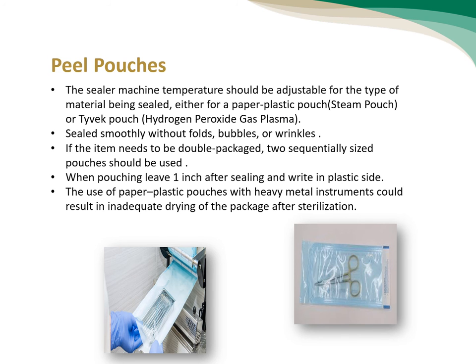One, peel pouch. We have to adjust the sealer machine temperature for the type of material being sealed. For example, if we are using a paper plastic pouch in the steam autoclave, we have to adjust it to a temperature higher than the one used for hydrogen peroxide gas plasma. That one takes a lower temperature. Again, we have to be sure that the sealing is smooth, without folds, without bubbles or wrinkles.